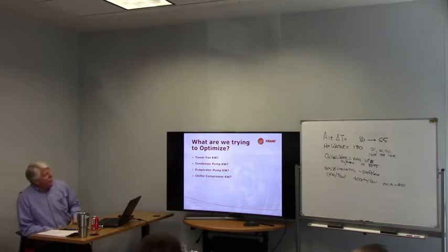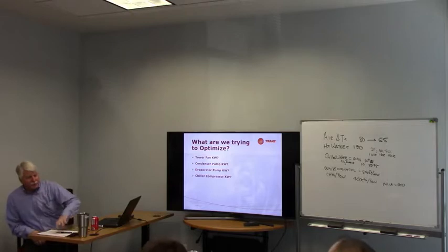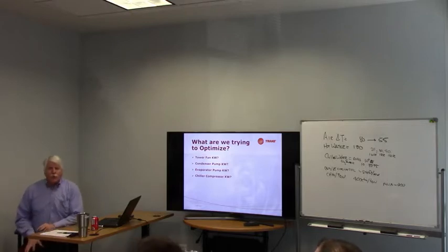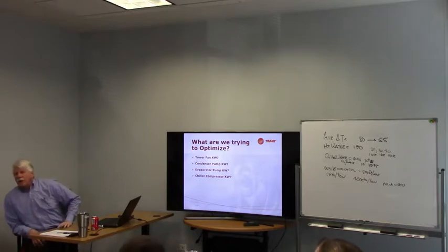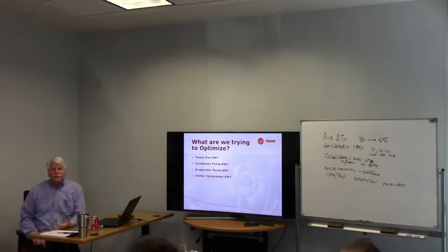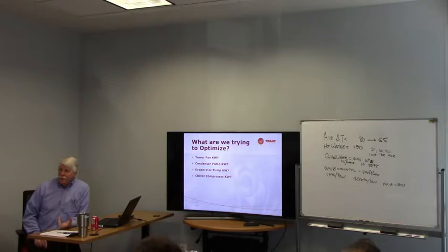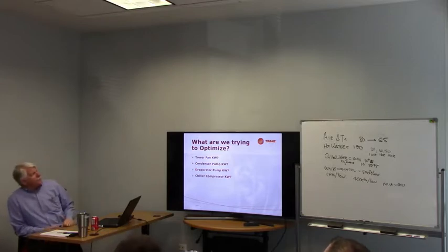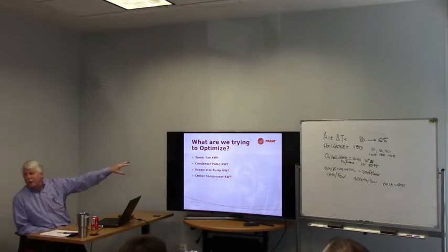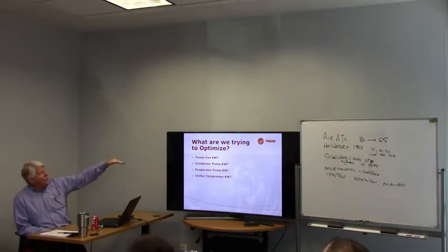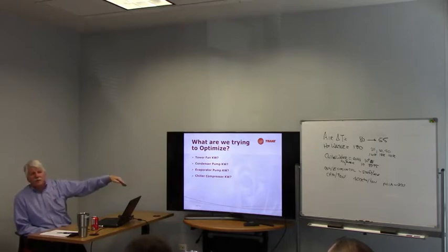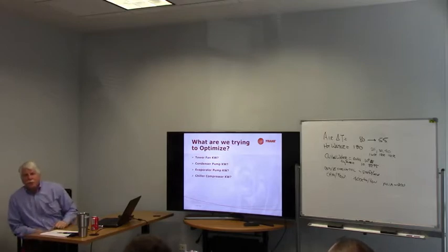All right. The next thing here is a presentation I gave to a group of people a couple of years ago about chilled water system optimization. Okay? And we talked earlier about a 10-degree delta T on the chilled water and a 10-degree on the condenser water. Those are very, very old school numbers, and we shouldn't be using them today for good design. Okay? But for this presentation, we're talking about what we want to optimize on a given building. Do you want to minimize the tower fan KW? We're looking at just chilled water systems here. Do you want to minimize the condenser pump KW? Do you want to minimize the evaporator pump KW? Or do you want to minimize the chiller compressor KW? Which one of those do you want to minimize?